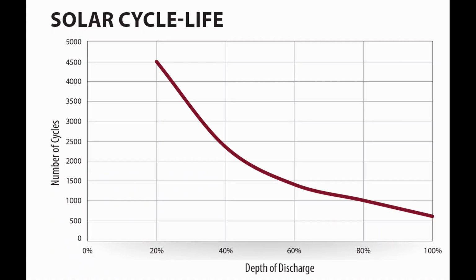Here is a typical cycle life chart for a high-quality solar AGM battery. This happens to be from Trojan. Here we can see that when cycled by 20% state of charge, the cycle life is 4,500 cycles. At double that, 40%, the cycle life is about 2,300, or about 1/2. Likewise, if you use 80% of the battery down to 20% state of charge, the cycle life is 1,000. And if you use half of that, the cycle life is 2,300. Again, the effect is about linear.